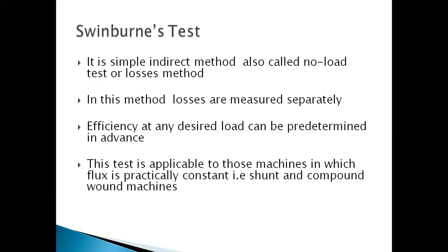In this method of testing, no load losses are measured separately and we can determine the efficiency. Efficiency at any desired load can be predetermined in advance. This test is applicable to those machines in which flux is practically constant, that is, shunt motors and compound wound motors.